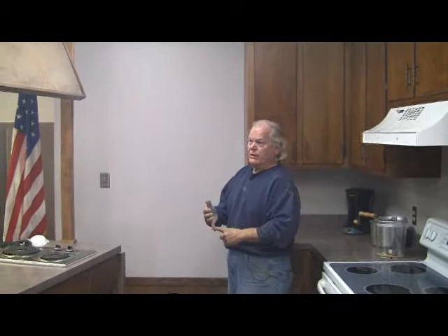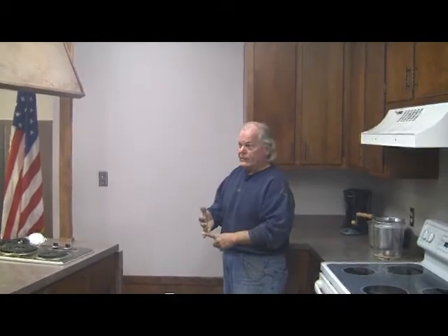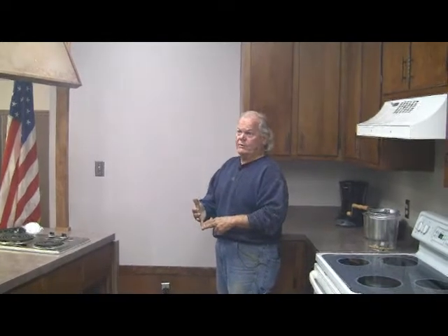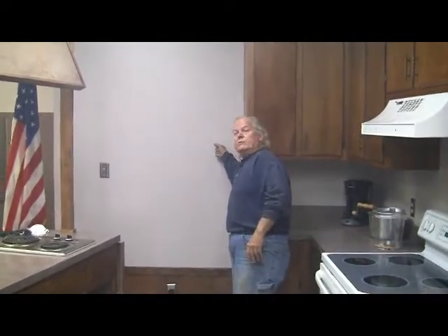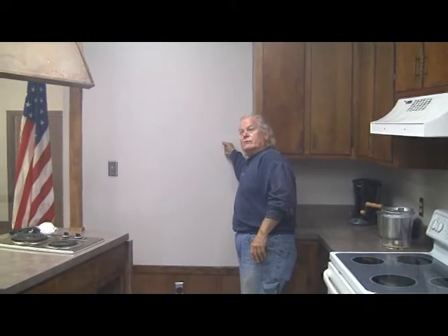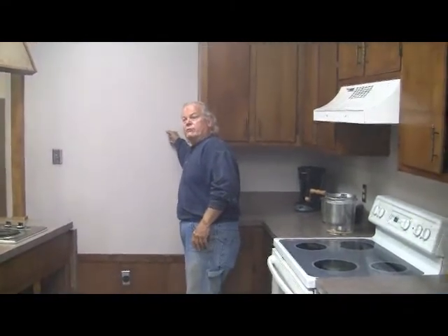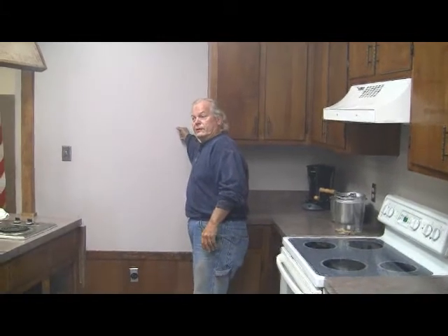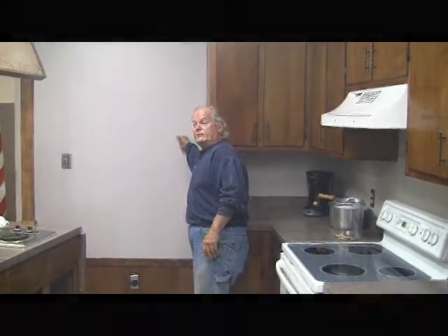In the summertime, we're looking at warm, moist air. We not only have to cool it, we have to dehumidify it. In the wintertime, we're looking at cold air that we're heating back up to whatever the comfort level is inside this room, and we're trying to pull it down this wall. So when we're using building cavities as return systems, we've got to completely understand how we want to seal them off so that we don't pull conditioned or unconditioned air from outside.